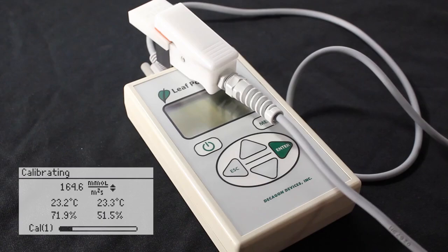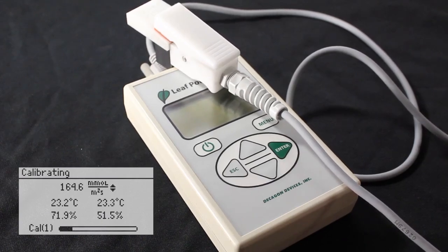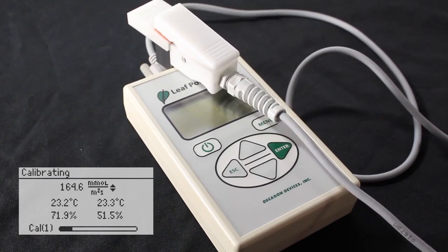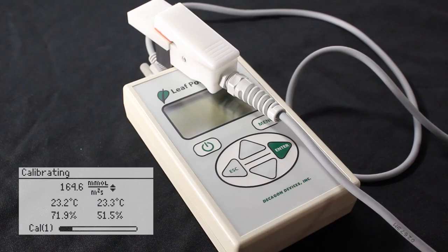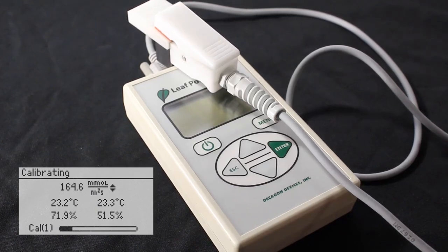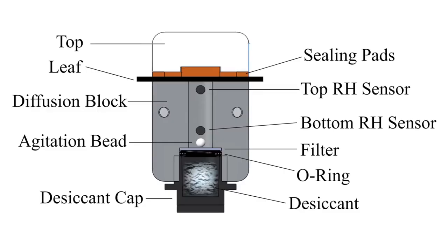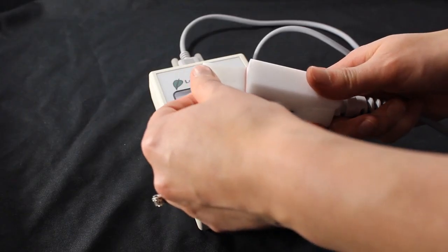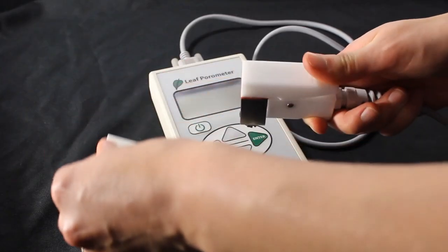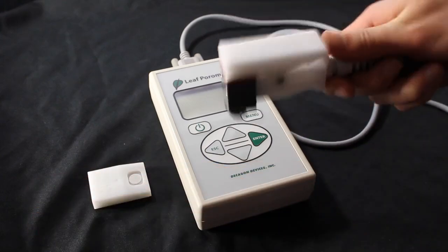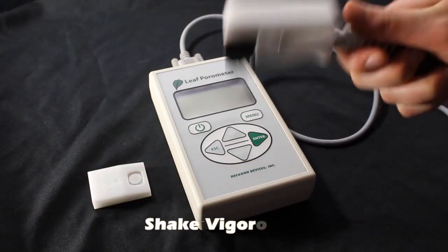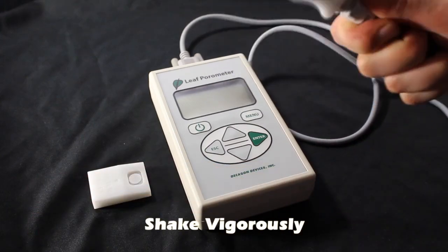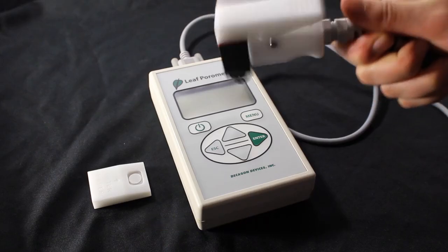While the sensor head is in measuring mode, be sure to align it so that the aluminum block is facing down. Take caution not to shake, tilt, or touch the metal block on the sensor head while the measurement is being taken. This ensures that the bead will settle to the bottom and not interfere with the diffusion path. After 30 seconds, the measurement will be completed, and the porometer screen will prompt you to equilibrate the two humidity sensors once more. Again, do this by waving the sensor head in a vertical motion in order for the bead inside the chamber to mix the air.